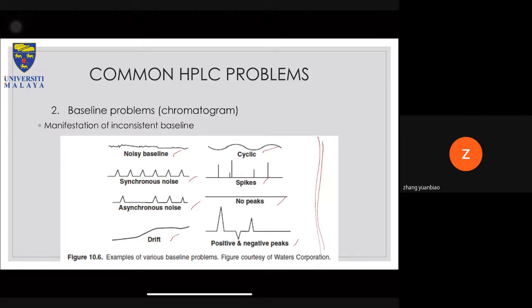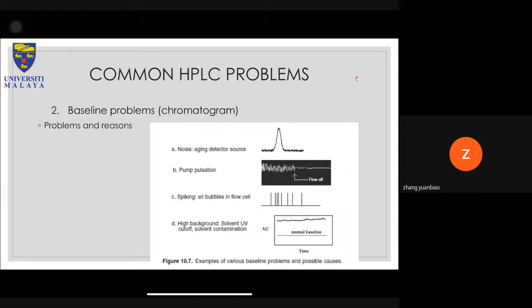Okay, moving back to the baseline problem. Some problems and their reasons: if you have some noise like this or any other noise, as I showed in the previous slide, you might have an aging detector source. Detector source means that if you are using a UV-vis, your lamp might be broken, or it's already too old to give you a consistent light source.